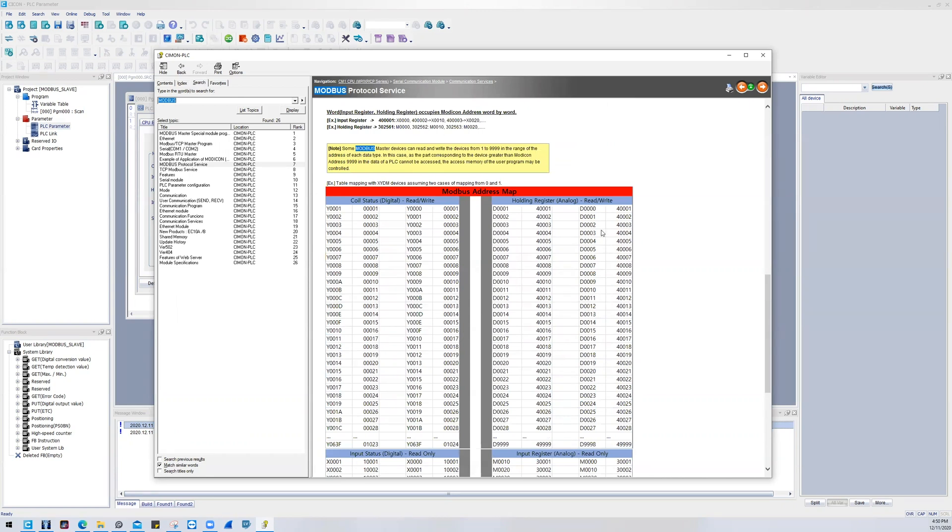So D's literally just map one-to-one but with an offset of 1. So D0000 maps to 400001, and then so forth all the way down to the max. So it's just an offset of 1 for each register.